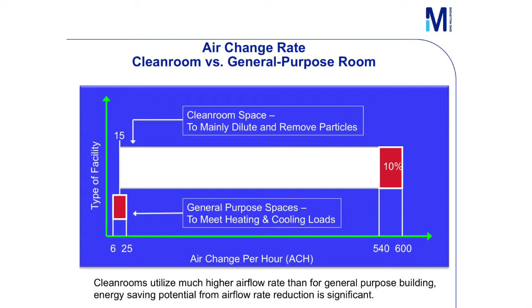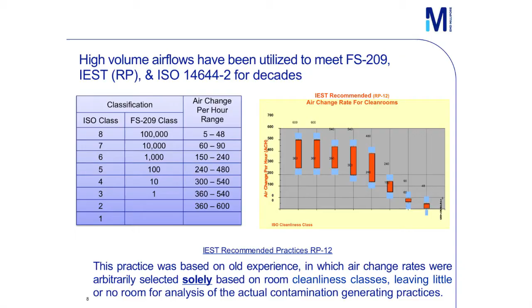These are some charts I stole off the internet, but that's a Class 7 clean room. It's actually ISO 7, Class 10,000, and they recommend 60 to 90. So if I'm the engineer, I'm going to sit down and draw everything, design all my fans, my ductwork, et cetera, to give you 90 or maybe more air changes per hour. So it's really based on old practices, and really, it's not based on any fact. We didn't really want to settle for that. We wanted to challenge ourselves. We felt we could get innovation points for LEED. So we started to look at what we could do.